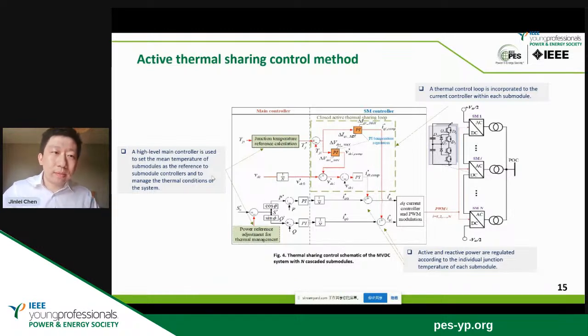To balance the thermal stresses among modules, I superposed a thermal controller on the traditional DC voltage controller. We can see that the high-level main controller collects all the junction temperatures from submodules, and then sets the mean temperature of submodules as a reference to submodule controllers. There are two thermal PI regulators: one regulates the reactive power of the submodule, and the other regulates the active power of the submodule. They jointly redistribute the thermal stresses among submodules, and by using the thermal sharing control method, the thermal stresses are equally shared by submodules, and they have the same lifetime.